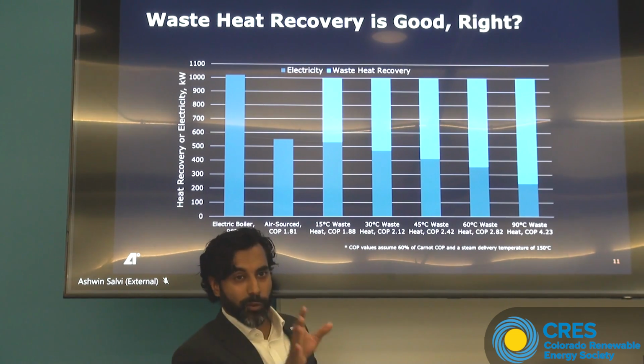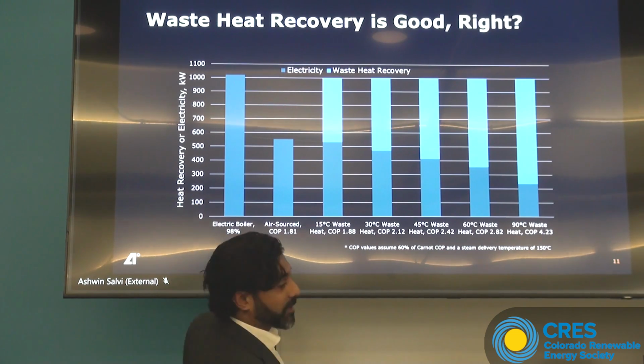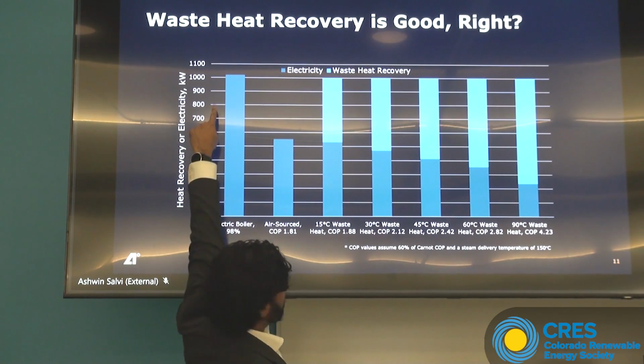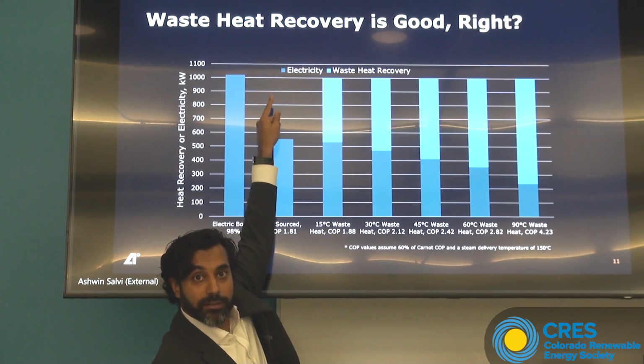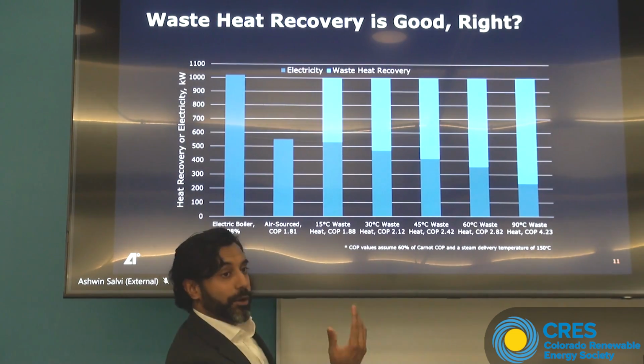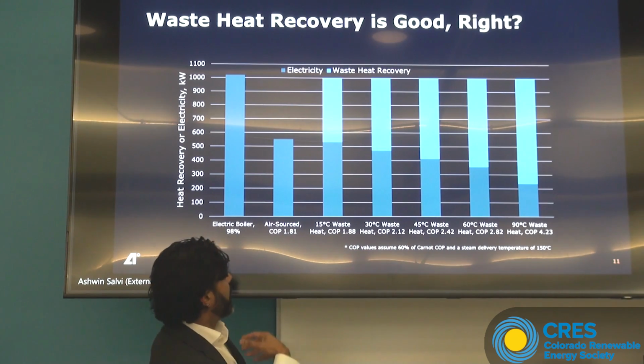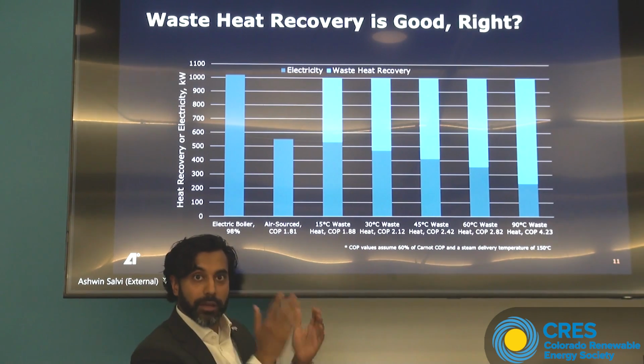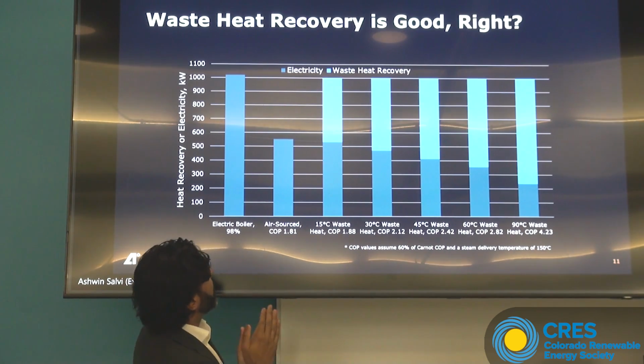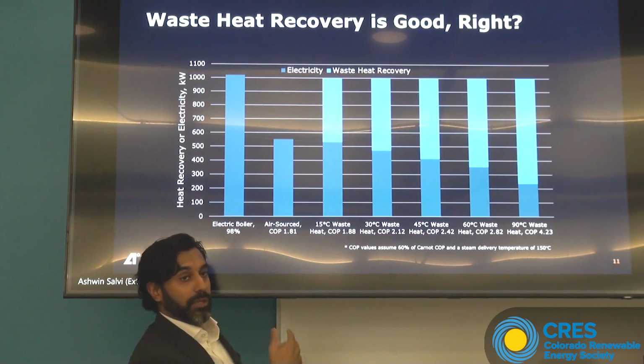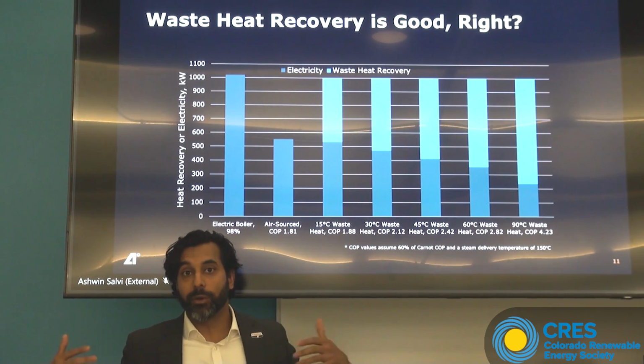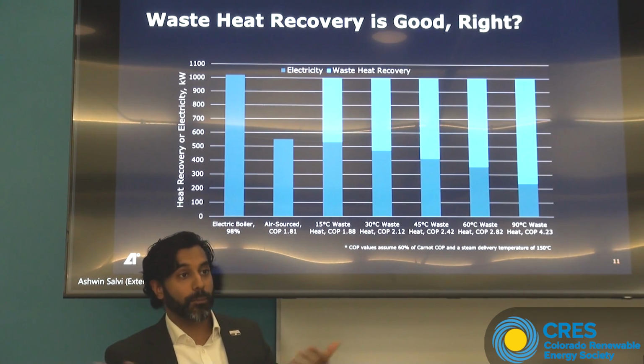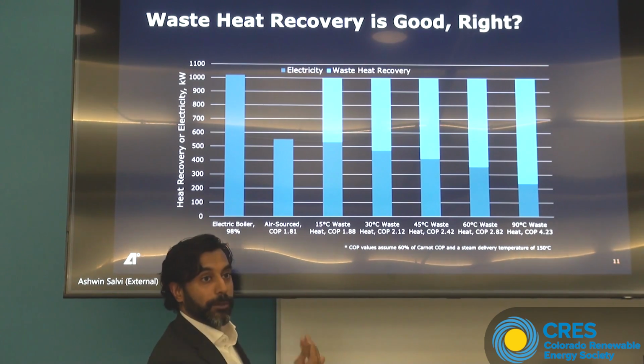In this case, we're trying to make 1 megawatt of steam. If you have an electric resistance boiler, you're consuming that much in terms of electrical, which is why it's expensive to run. If you have an air source system like the AtmosZero system, in ambient conditions like you'd expect in Fort Collins, we cut that electricity consumption down by half. This is why we're operationally more efficient and more cost effective than an electric resistance boiler.